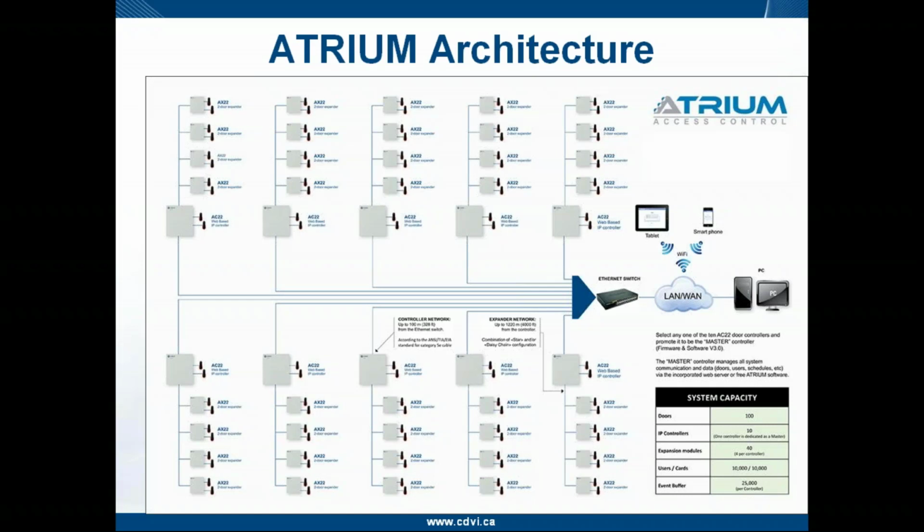Now, I'd like to maybe explore the differences between a controller, whether it's a master or a subcontroller, and a door expander. A door expander is the same part number, the same physical board. It's just a matter of changing a jumper on the control panel itself to change the A22 from a controller to a door expander.